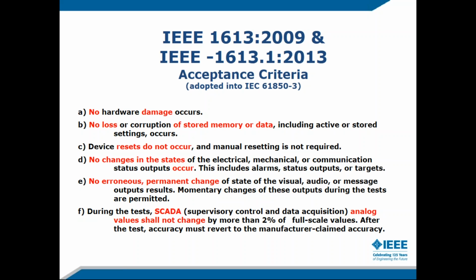Momentary changes are permitted, and then of course the supervisory control and data acquisition analog values shall not change by more than 2%. So now you have to have an instrumentation that somehow monitors percent of the SCADA changes. Well, good luck. That's not necessarily easy. And then after the test, the accuracy must revert back to the manufacturer's claimed accuracy. I thought this showed up both in the 1613 series as well as the 61850. So here we have international harmonization on at least the acceptance criteria.